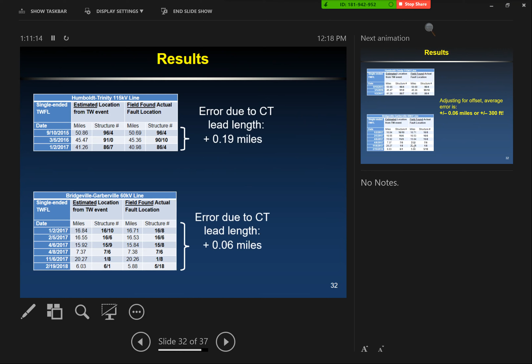Even here, when I look at the offset, there was a net offset of 0.19 miles in one case and 0.06 miles in another. If I accommodated for that, my error would have only been about plus or minus 0.06 miles, or 300 feet, for these cases. So if you accommodate for the lead length, you can get your accuracy down to about one span.